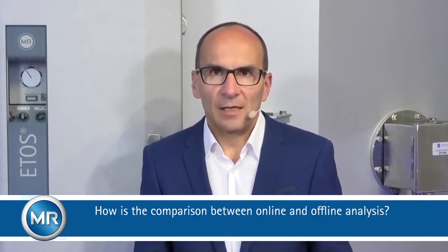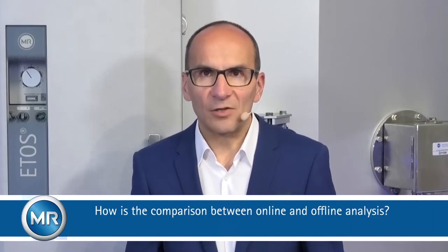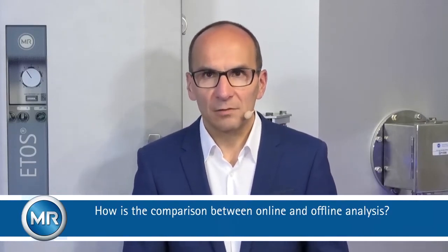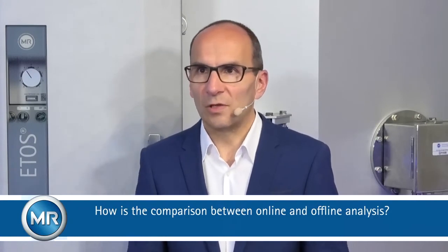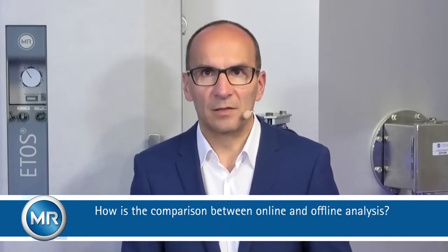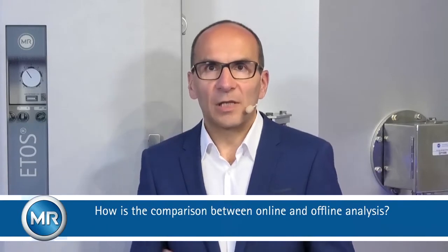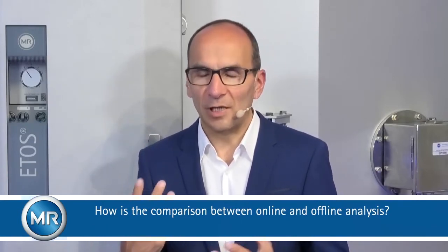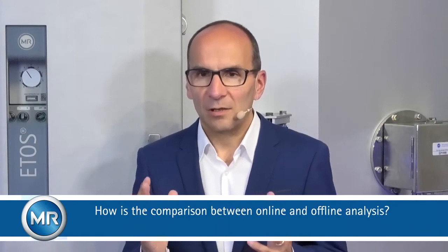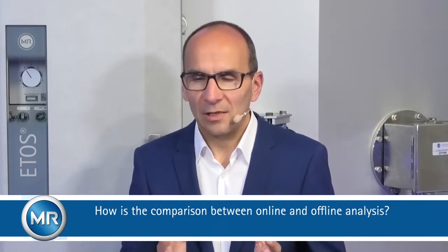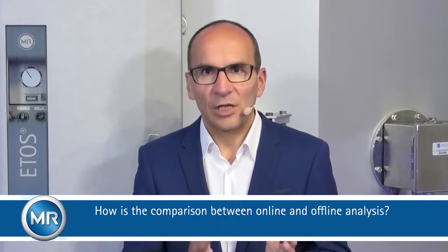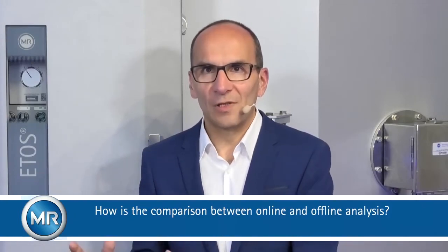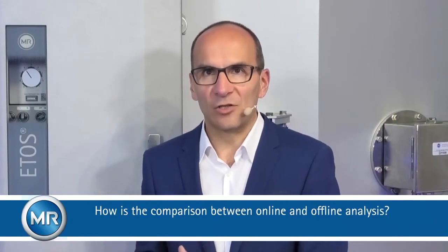Now, vibroacoustic diagnostic is a common method which is used in a similar way as DGA diagnostics. But the difficulty with diagnostics is you get a one-time picture, one incident. You have no reference for comparison. You do not know how this OLTC pattern has changed.